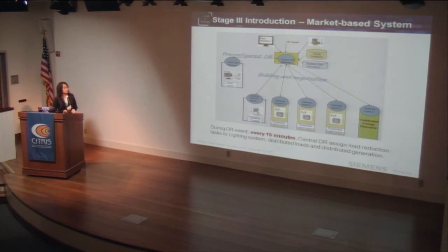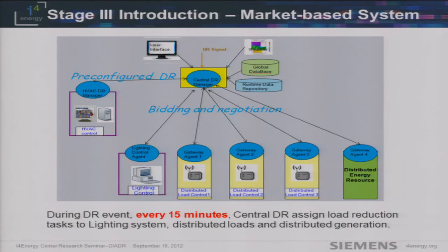And the way to do it is that during the DR event time, for example, 2 hours, we divide them into 15-minute intervals, and every 15 minutes, the Smart Energy Box would read from the building meter and compare that with our demand response goal. And if we still need to shed something else, then we go to the lighting and the plug loads.